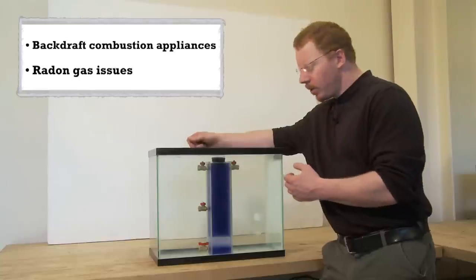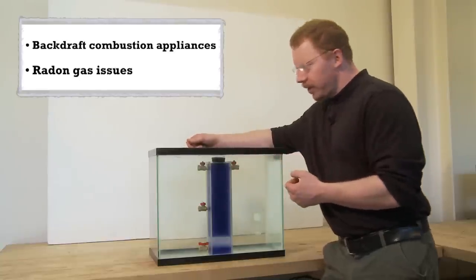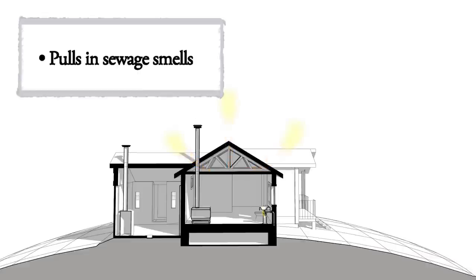Another good example of stack effect at work when you've got too much air leakage out the top is when you're bringing in sewer smells because a trap has dried up. When stack effect can't get enough air from other places, it's drawing it through the plumbing system, bringing that sewage smell into the house.